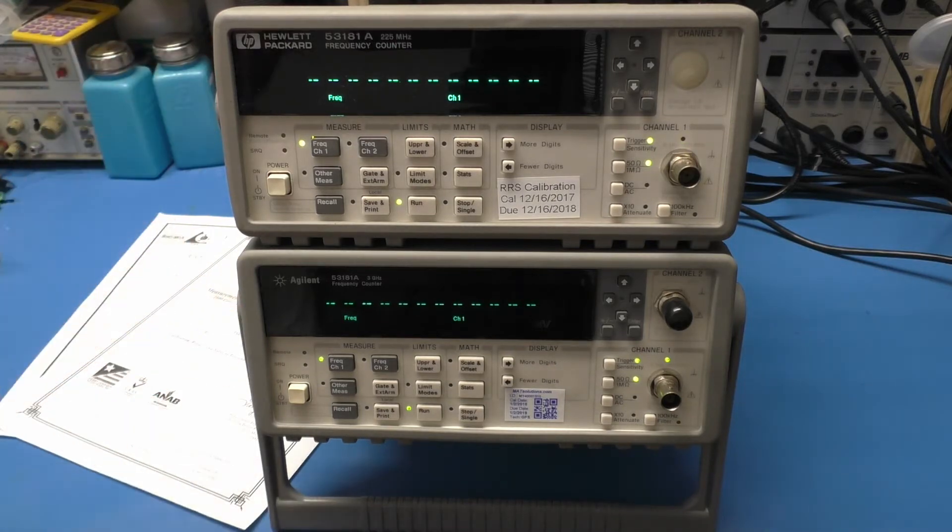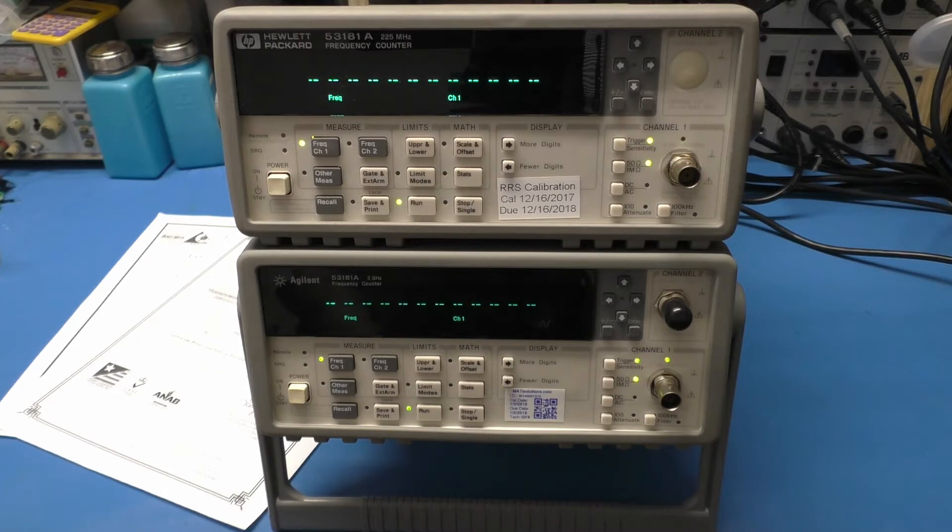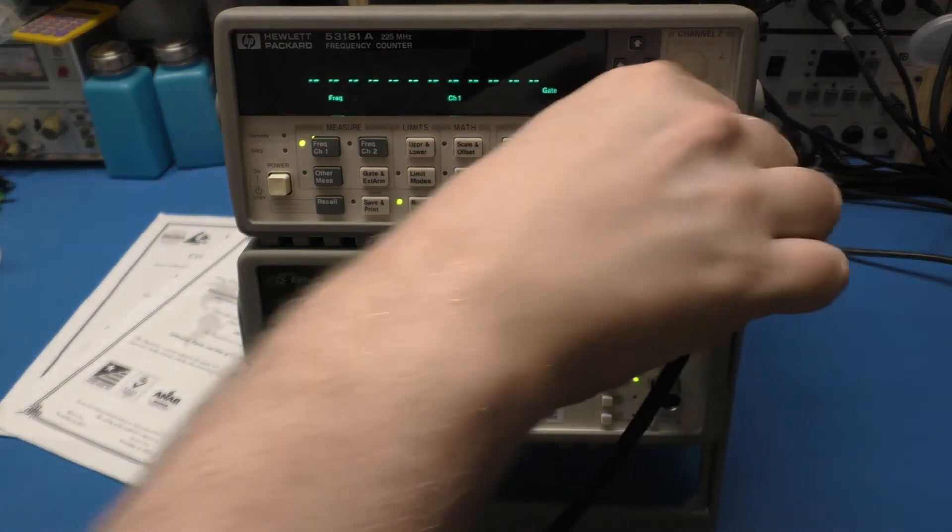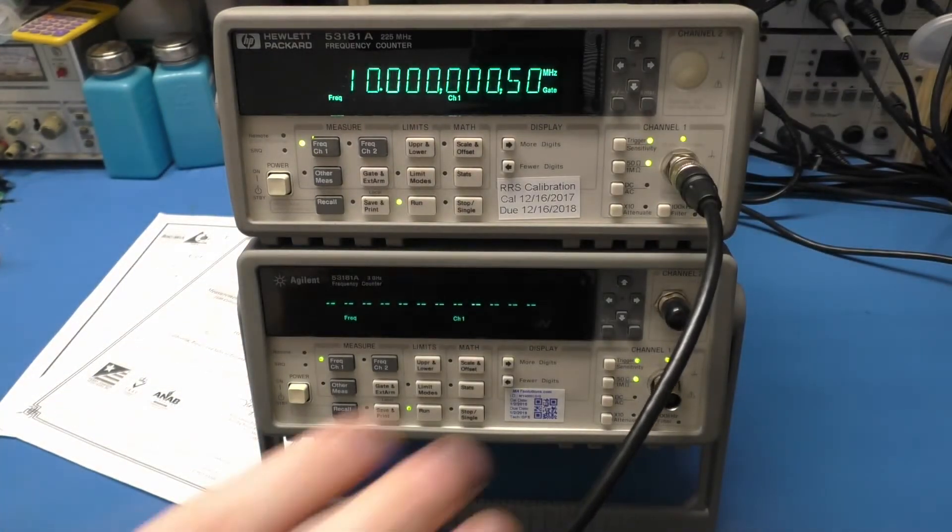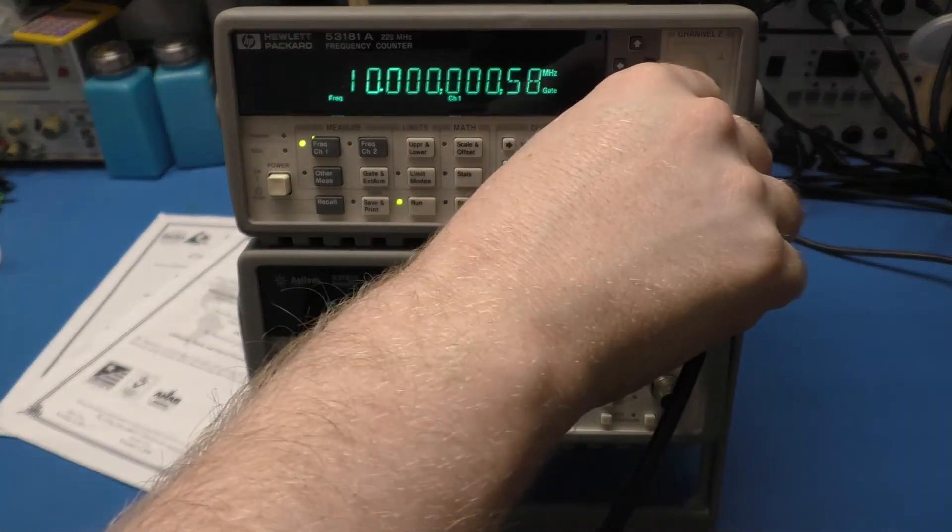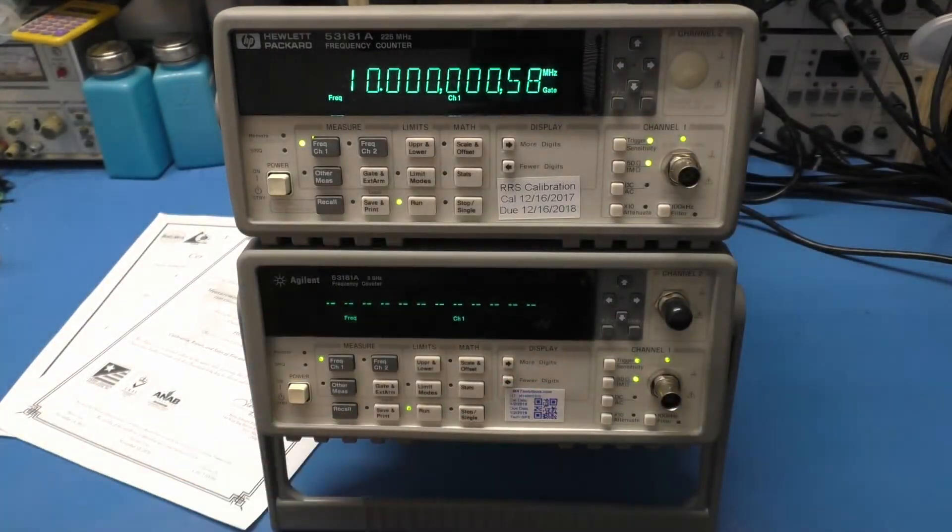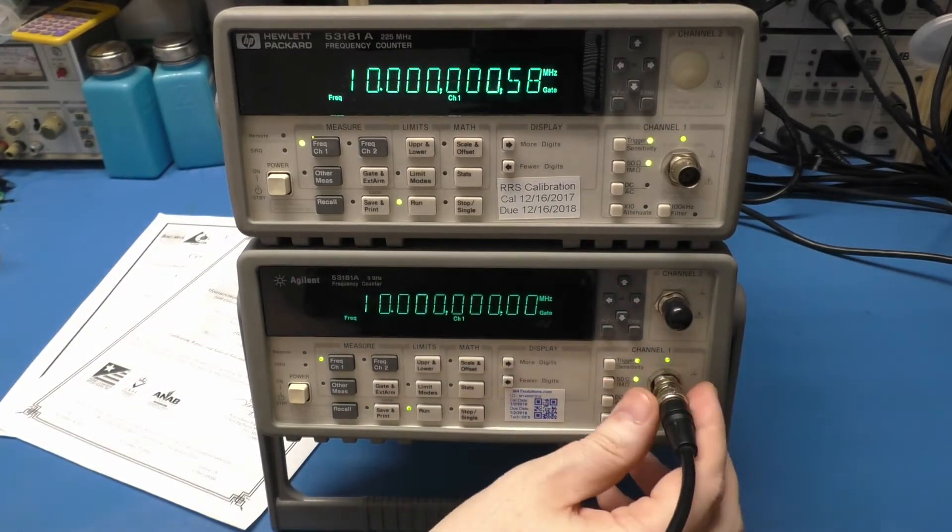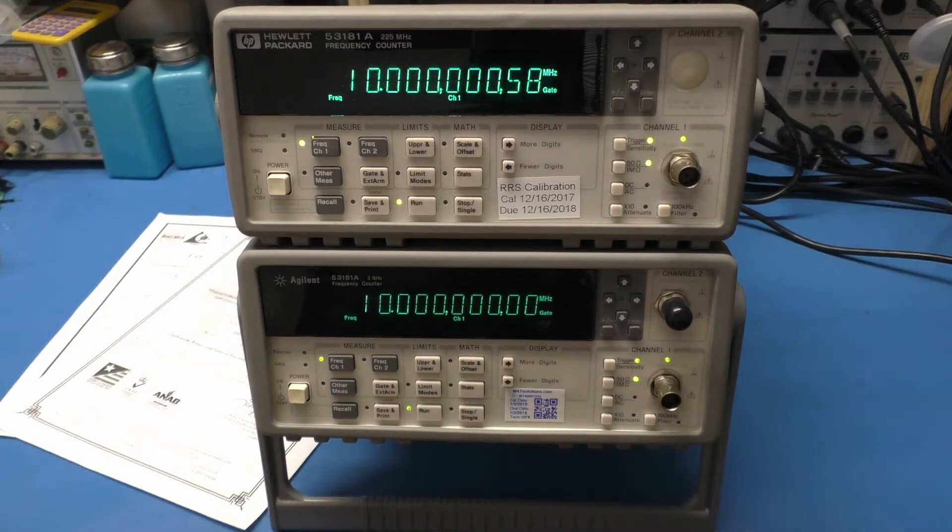So how do you know that the kit's good? With these two counters, the reason I picked the counter is because I could simply throw 10 megahertz into it from my GPS-based disciplined oscillator and see if I get 10 megahertz on them or how close I get to it. One is a trustworthy cal and the other one is not. This one is down on the money. Not surprised.